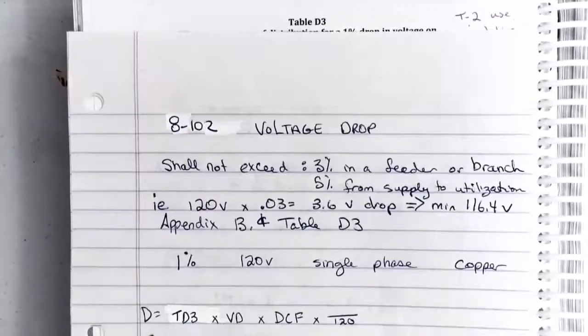The main formula that we use is D for distance in meters, and this is going to be the maximum distance that we can take that wire without exceeding the voltage drop. Table D3 - in table D3 are what I call the basic meters. So the basic distance that you could go with a certain size AWG, and we're going to adjust that using this formula, but we have to put the basic meters in here from the table.